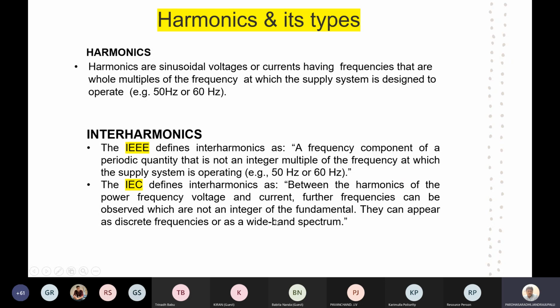We all well know about the 50 Hz system and the 60 Hz system. So what about 90 Hz? What about 120 Hz? What about 130 Hz? These are said to be interharmonic components. Multiples are called simply, first order is 50, the fundamental frequency, second order is 100, third order is 150. Likewise, we are saying that the harmonic number is there. But there are other frequency components that appear in the power system, and those are called interharmonics.